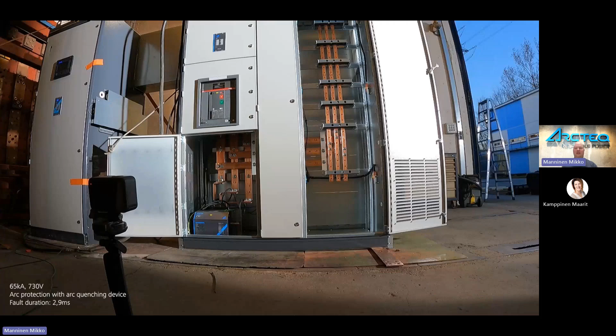The next one is then filmed from front, and this is another standard, actually a 2020 released IEC technical specification 63107, which states requirements for integration and testing of arc quenching devices or internal arc mitigation systems in low voltage switchgears and control gear assemblies, if I remember right. Yeah. So we did this in many ways, and we also performed this in a quite unique way. We wanted to go beyond the standards and we performed this testing also doors open.